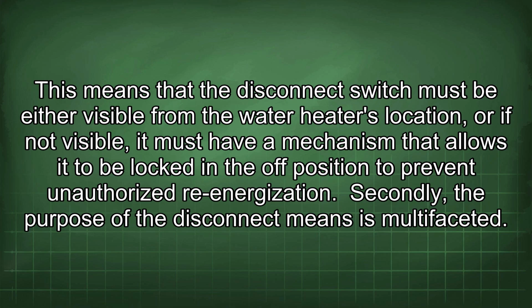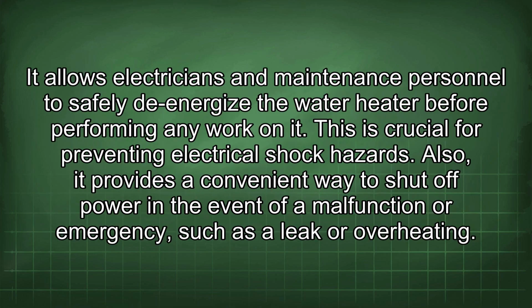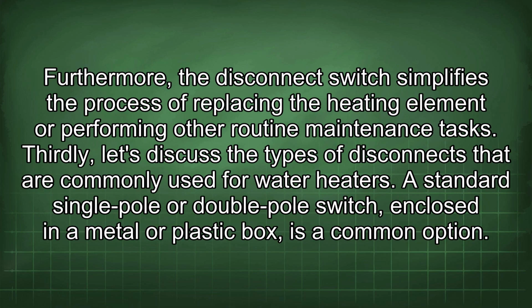Secondly, the purpose of the disconnect means is multifaceted. It allows electricians and maintenance personnel to safely de-energize the water heater before performing any work on it. This is crucial for preventing electrical shock hazards. Also, it provides a convenient way to shut off power in the event of a malfunction or emergency, such as a leak or overheating.